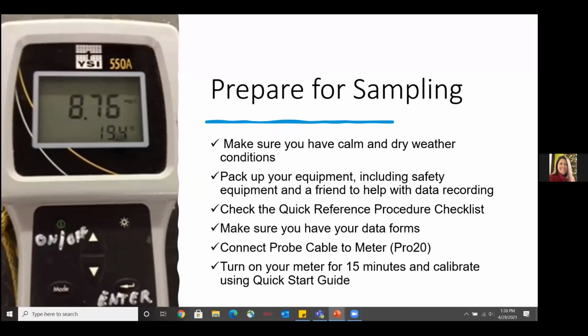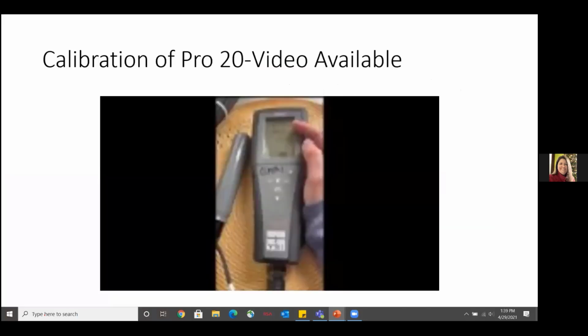And if you have a Pro 20, just make sure that your cable is connected to your meter. And if you have a 550A, you're going to need to turn on your meter for 15 minutes. The Pro 20s don't require that. The mechanics are different. But with the gray ones, you need to make sure you allow them to warm up for about 15 minutes before you calibrate them using the quick start guide. And now I'm going to show you two videos of how to calibrate your meters. First, we're going to start with the calibration of the Pro 20.